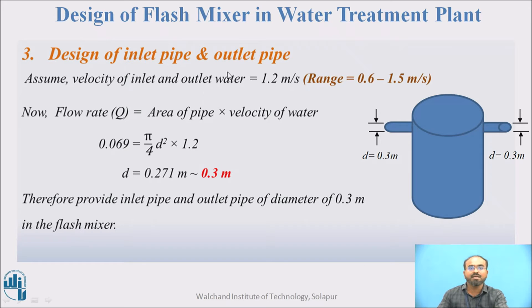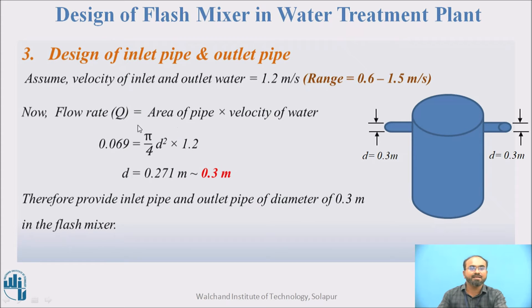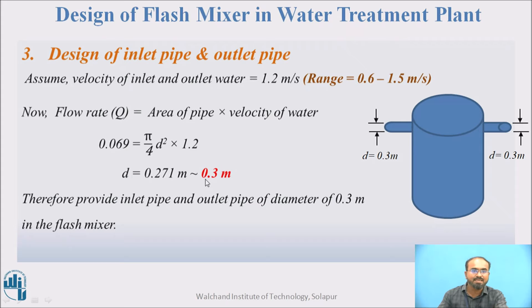For the inlet and outlet pipe design: the velocity of influent and effluent water is generally kept the same — I am taking 1.2 meter per second, within the range of 0.6 to 1.5 meter per second. Using Q equals area multiplied by velocity, and knowing Q is 0.0694 m³/s, we solve for pipe diameter: 0.0694 equals (pi/4) d² multiplied by 1.2, giving d equals 0.271 meter. We round up to 0.3 meter. So the inlet and outlet pipe diameter is 0.3 meter.